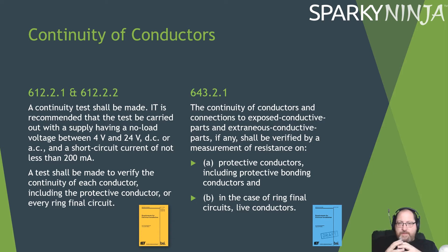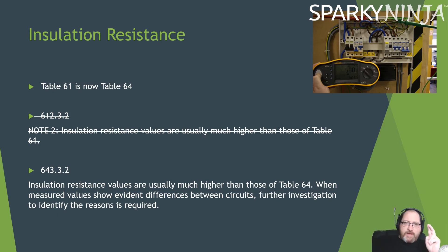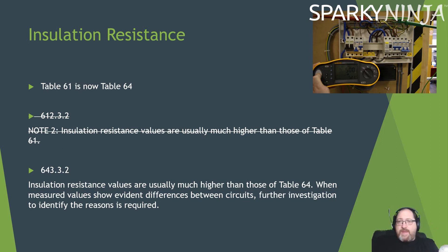They've taken the 4 volts, 24 volts, 200 milliamp specification out, which is annoying because that might have to disappear from exams. Table 61 is now Table 64 — that's fine, it's the first table in Chapter 64. The old regulation had a Note 2 to 61232 saying the insulation resistance values are usually much higher. That's now been introduced into the regulations proper, not just in a note. It says the values are usually much higher than those of Table 64, and if they show evident differences between circuits, further investigation to identify the reasons is required.